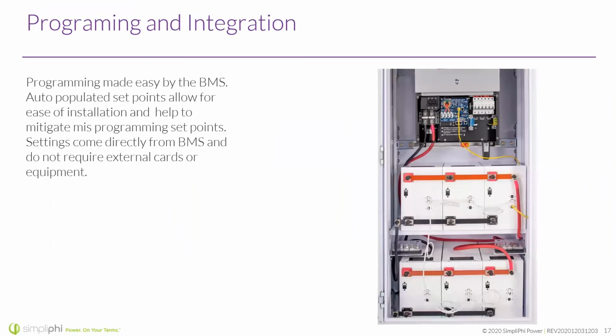So programming on that side of things is made easy by the battery management system. As we talked about, the auto-populated set points allow for this ease of installation and help to mitigate misprogramming set points. The settings come directly from the battery management system. And as I mentioned, they do not require external cards or equipment. The battery management system has that data, has that comms capability built in.